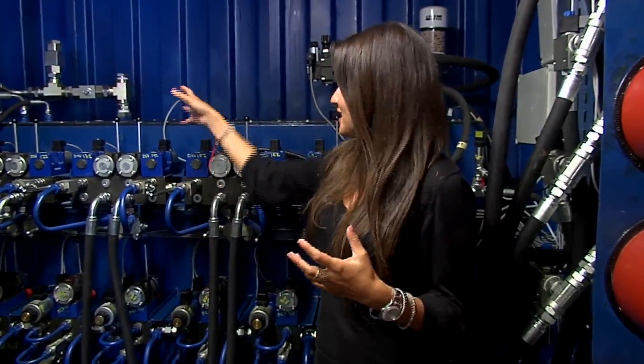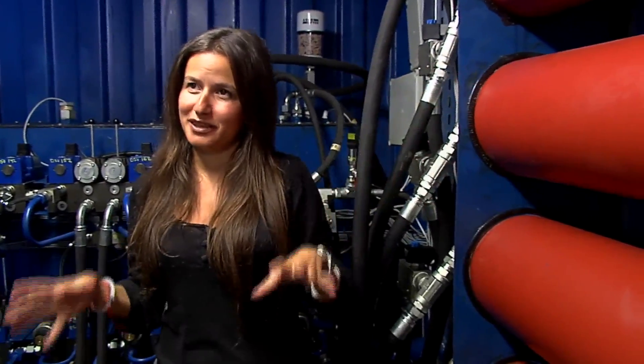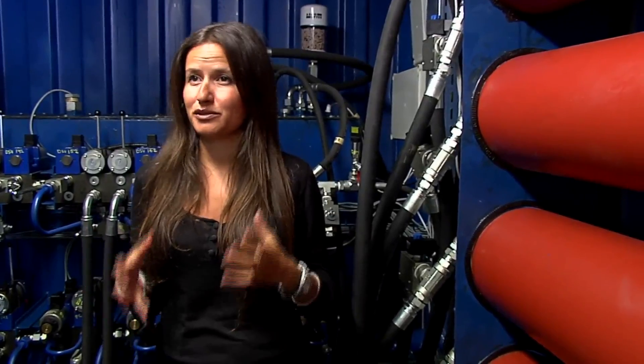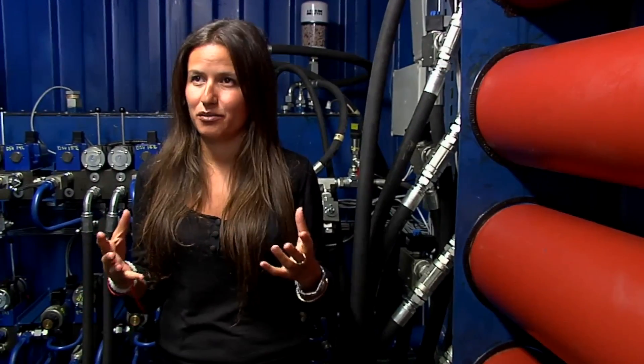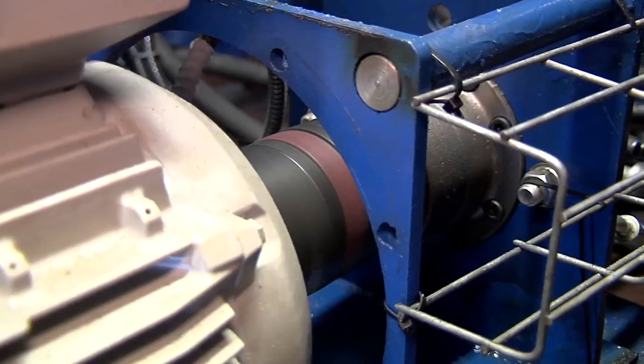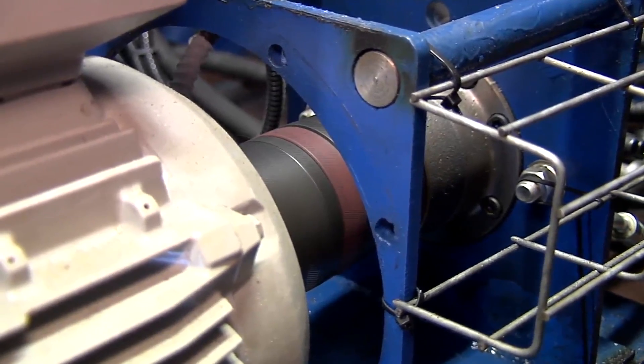When the floaters are going up and down with the hydrocylinders, they're taking oil from this tank and pushing it into the accumulators. The accumulators are partly filled with oil, partly filled with nitrogen. This mixture of the two is creating pressure that is very, very strong and can range between 50 bar in low waves to 160 bar in higher waves. That pressure is used to turn the hydromotor, and these hydromotors are turning the generator.